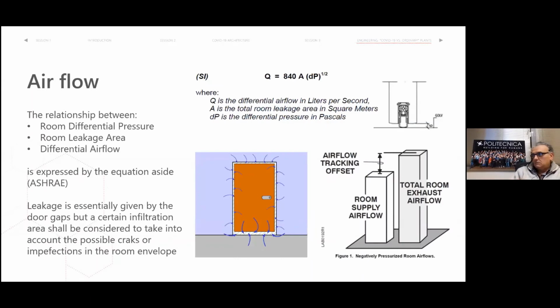Okay, so why do we need to provide a different supply flow with respect to the exhaust airflow? The example that is now shown is the negatively pressurized room. So this is for the COVID-19 intensive care unit. So the supply of the air to the room is lower than the exhaust airflow. In this way, we will have an under pressure inside the room, which is covered by infiltration along the border of the door, or at least some imperfection of the envelope.